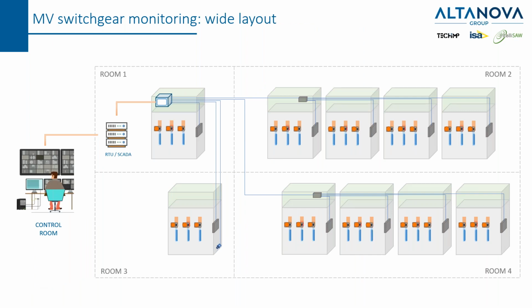Once the system becomes more populated and the monitoring system requires monitoring more medium voltage panels, of course, you can refer to only one local HMI, and then connect all the other medium voltage switchgear through the reader and the related antennas and sensors. Everything, of course, from the HMI can be connected to an RTU, and using a standard industrial protocol, for example Modbus, the information is delivered to the control room, where there is the main SCADA for the operator to check the status of all medium voltage switchgear.